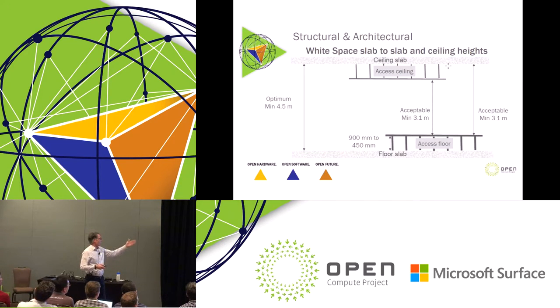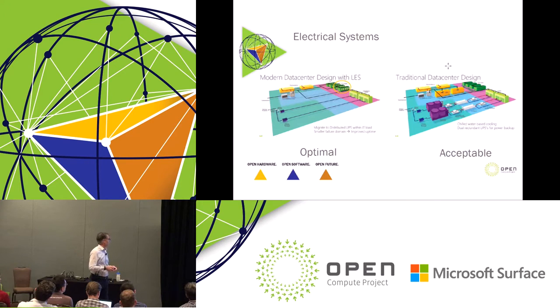We try to give some guidance of what it would be great to have, but if you can't achieve that then you can get away with 3.1 meters. We've also looked at the space under the access floor and given some guidance around 900 millimeters if you were using that as a cooling pathway, but if not then 450 would be sufficient.